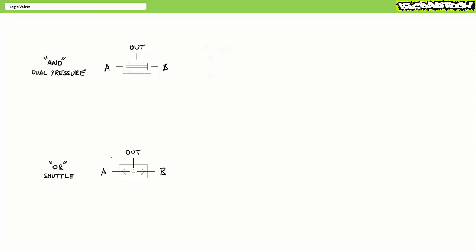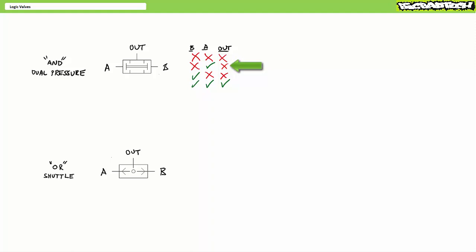Both valves have two inputs and one output. An AND or dual pressure valve works like this: there must be a pilot signal at both inputs A and B for there to be an output. A red X symbolizes the absence of an input or output, whereas a green check mark symbolizes the presence of an input or output. When neither A nor B receive an air pilot signal, the AND valve produces no output. When only A receives a signal, no output. When only B receives a signal, no output. Only when both A and B receive an air pilot signal does the AND valve produce output.